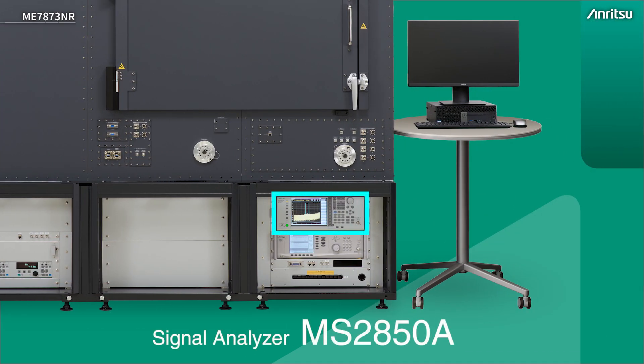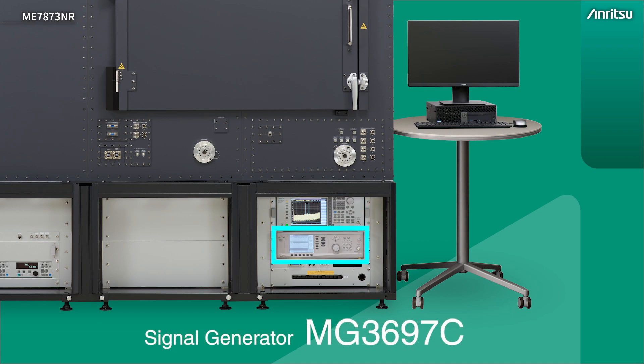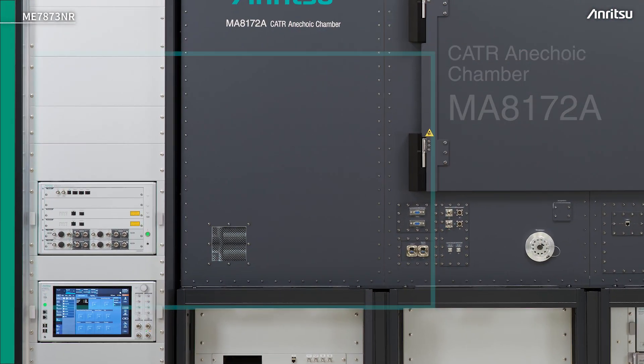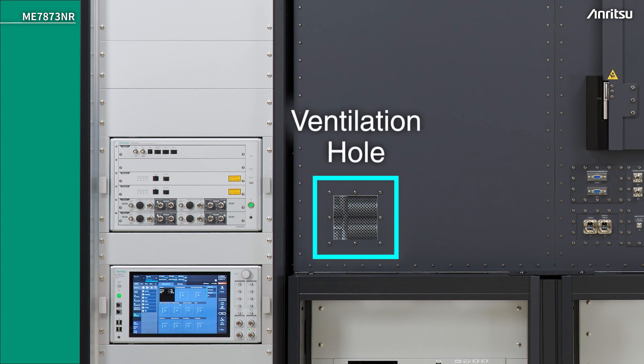On the right-hand rack, there's a signal analyzer similar to the FR1 but with a higher frequency range, and a CW signal generator as well. In terms of the chamber itself, it's a CATR — a compact antenna test range chamber. This means we operate in a far-field type measurement situation, using a reflector to create that measurement path length but in a smaller physical volume and length. The chamber also has vents on the front and rear that allow hot and cold air to be pumped in for extreme temperature conditions. Anritsu supports those and is developing equipment to be ratified by 3GPP RAN5.